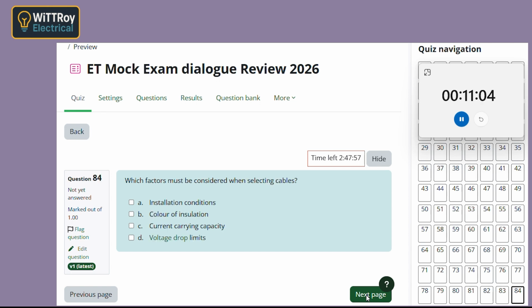Question 84. Which factors determine cable selection? Current rating and installation conditions? Yes, and also voltage drop. All three are important. So it's not just, can it carry the current? Exactly. You also think about how it's installed, like in insulation, underground, grouped cables, because that affects heating. And voltage drop limits. Yep, you don't want too much drop at the load. And color doesn't matter. Nah, that one's just there to distract you.